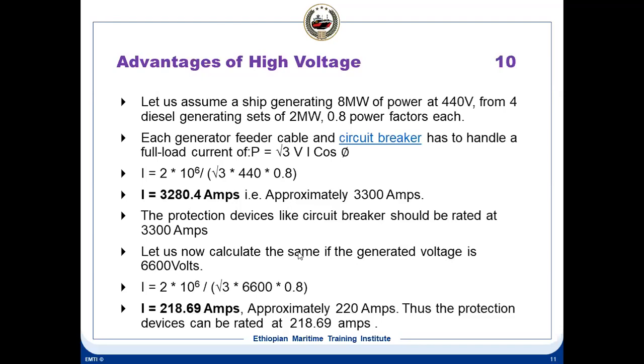Now, if you calculate with a higher voltage, then what happens? Let's calculate the same for a generator voltage of 6600 volt. With the same formula, I is equal to 2 into 10 raised to 6, that is the power, 2 megawatt, divided by √3 into 6600 into 0.8. Here the current drastically reduces to 220 amps. So the breaker which had to be rated 3280.4 amps at 440 volt now needs only 220 amps. So your breakers, cables, everything, the ratings come down if you use a higher voltage.